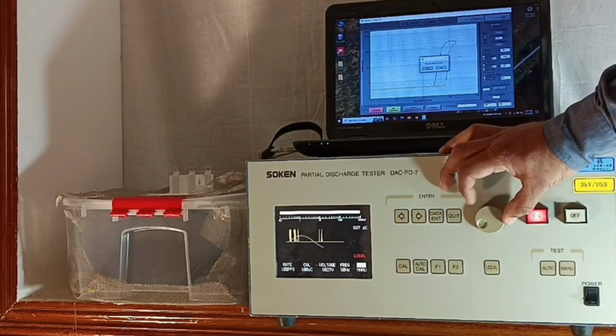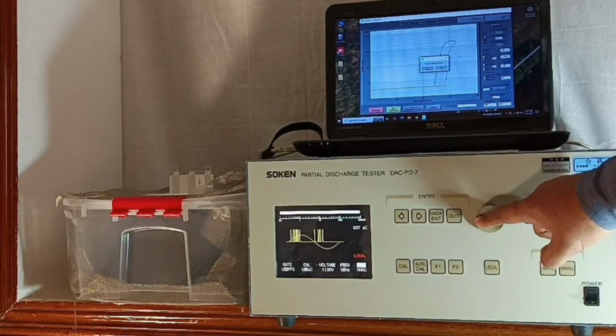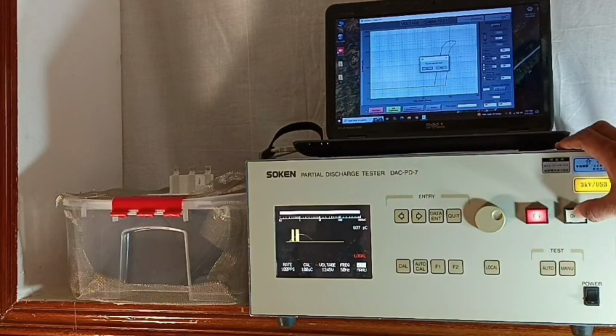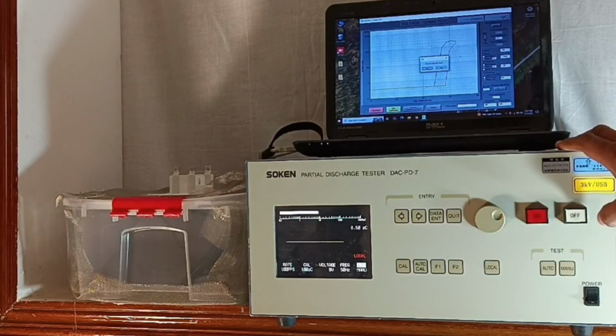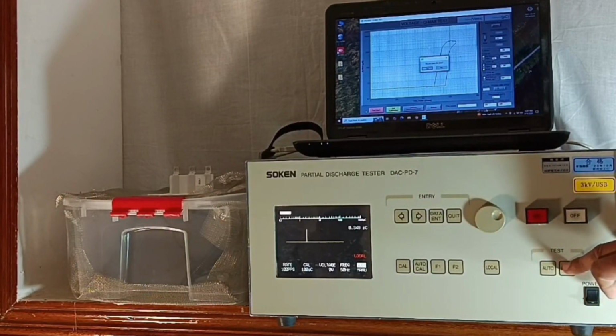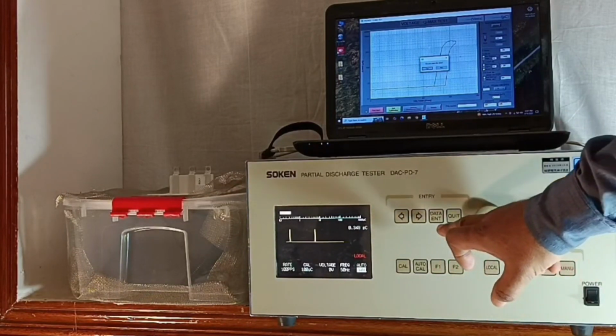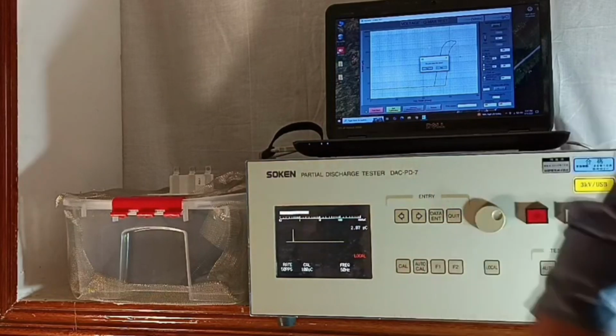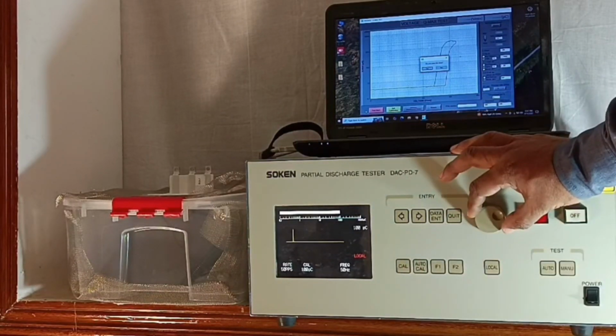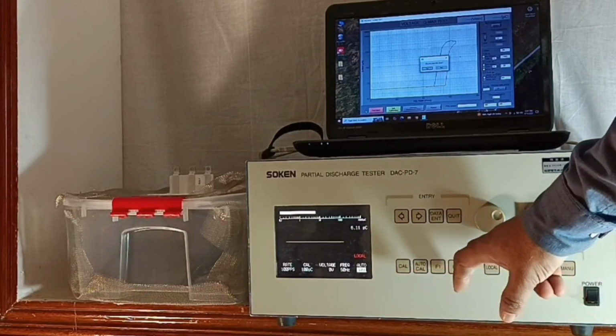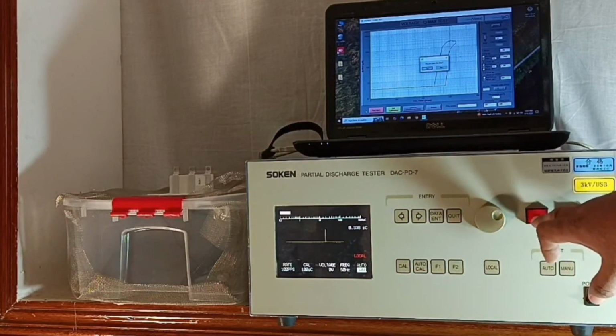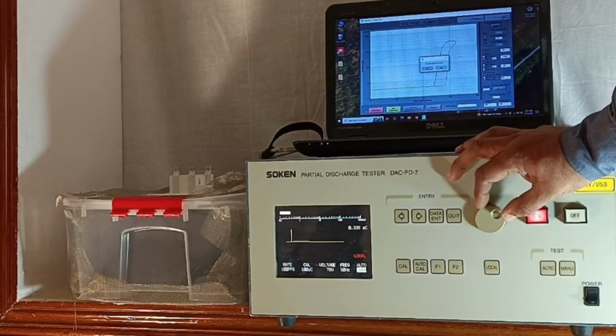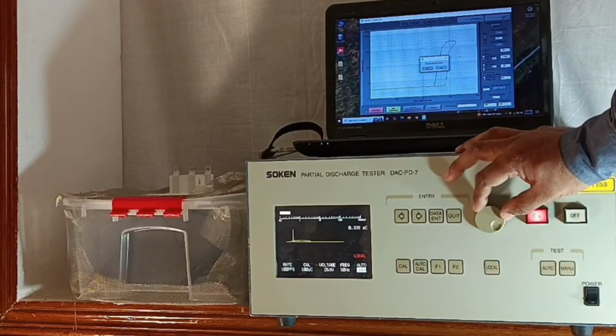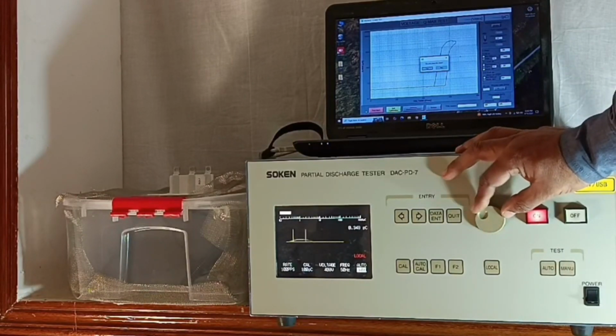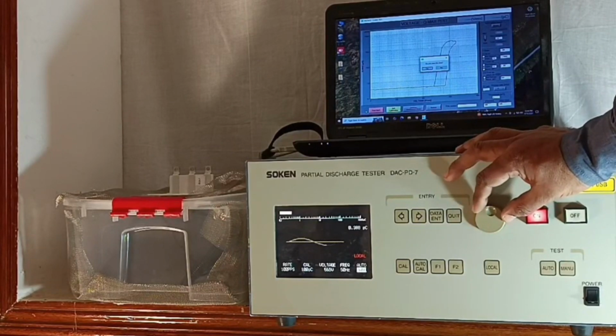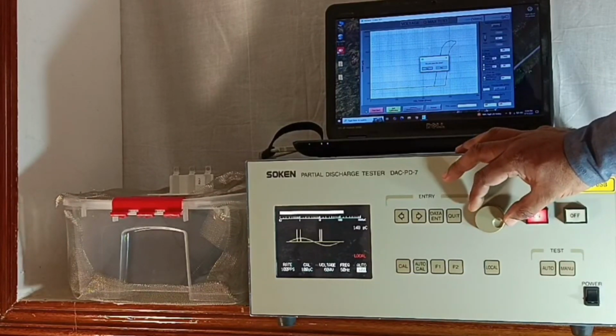Now the auto mode. This is on auto mode, so I have to do it in manual mode. So auto mode, again verify the calibration, done, good, and then apply the voltage. It is increasing, and so observe at what voltage the pC reading shoots up beyond. Now you can see it is approximately 600 volts.